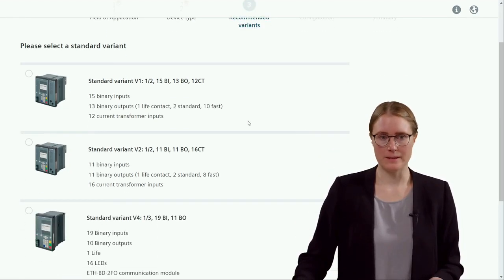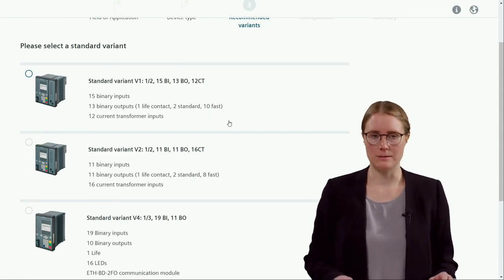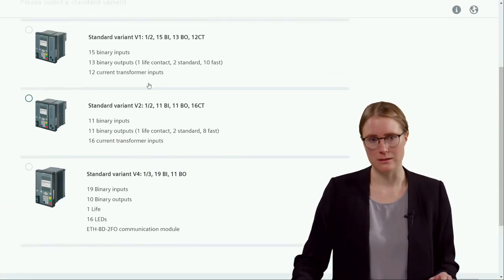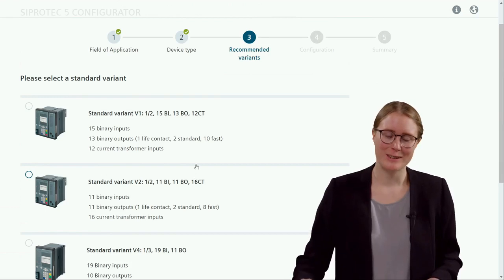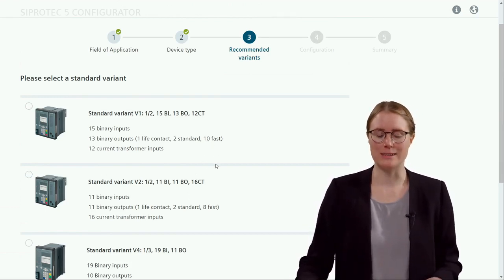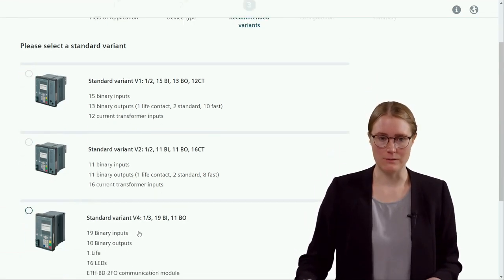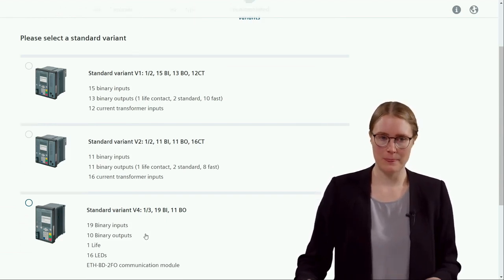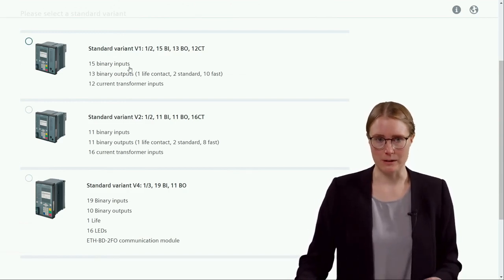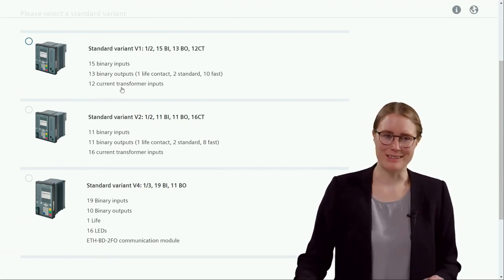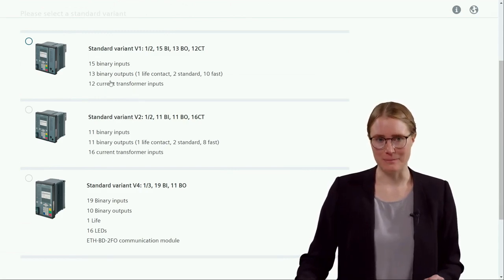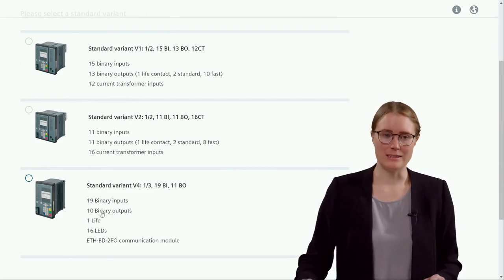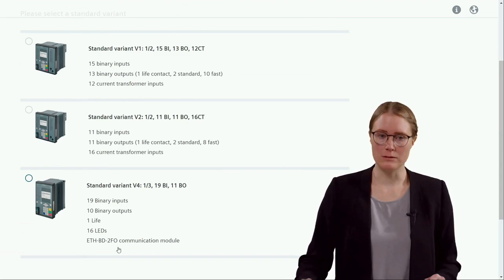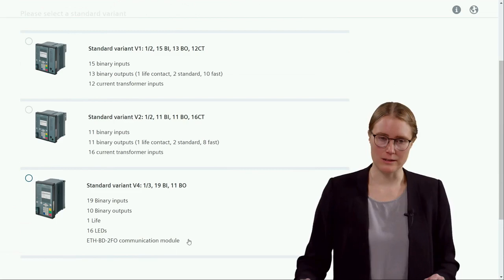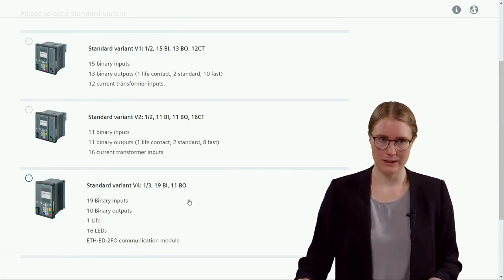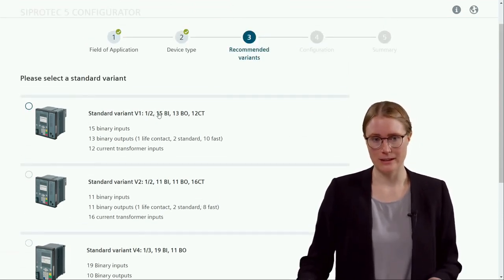Here you can choose the standard variant with which you want to start your configuration. There are 3 options offered here. The first 2 are interesting for the centralized configuration and the IEC 61850 compliance solution. The standard variant V4 is interesting for the distributed busbar protection, because as you see in this overview, you already see how many binary inputs and outputs are available, and how many current inputs are available. And for the last variant, the speciality is that there are no current inputs, but an Ethernet BD module for communication. That's why the standard variant V4 is the interesting one for the distributed setup. But in our centralized configuration, I go with standard variant V1 as an example.